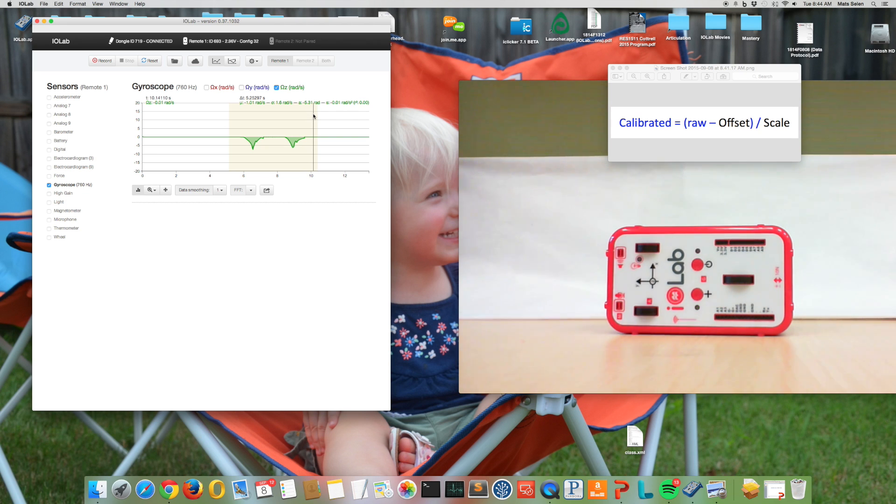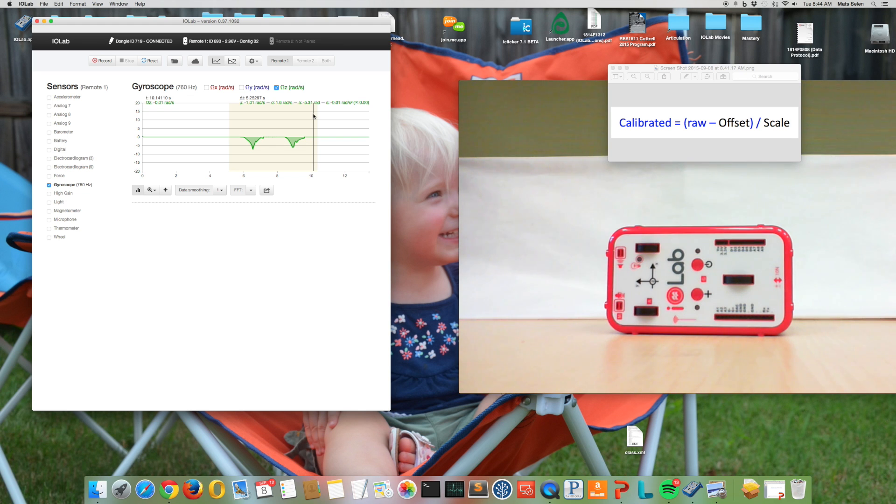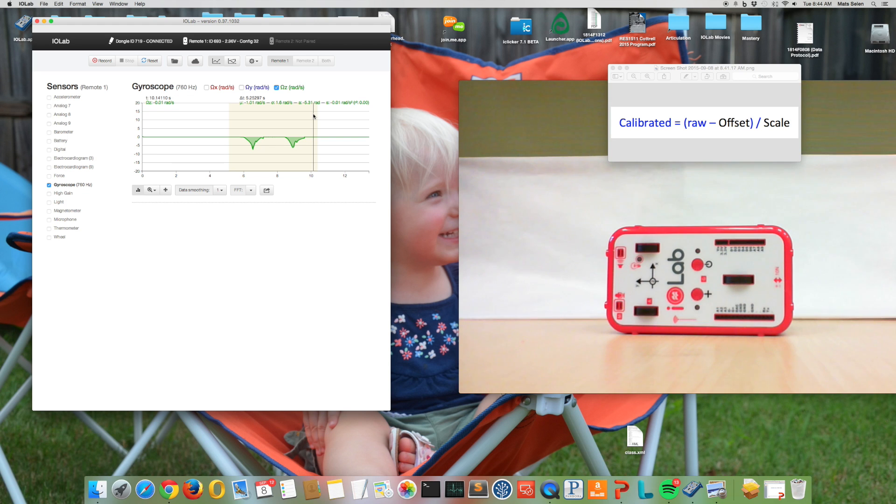So I need to fix the scale factor in my calibration by exactly that factor. So if I take my calculator and I do 5.31 divided by 6.28, I need to make that scale factor smaller by exactly a factor of 0.85.